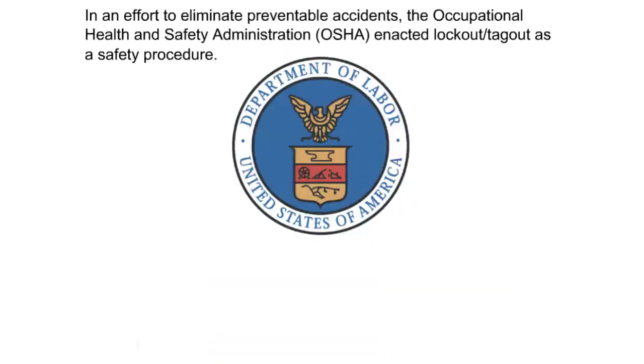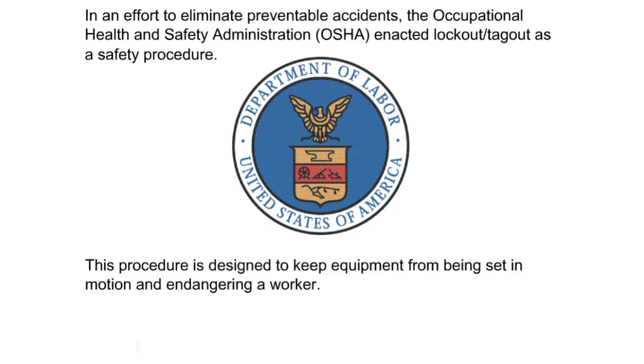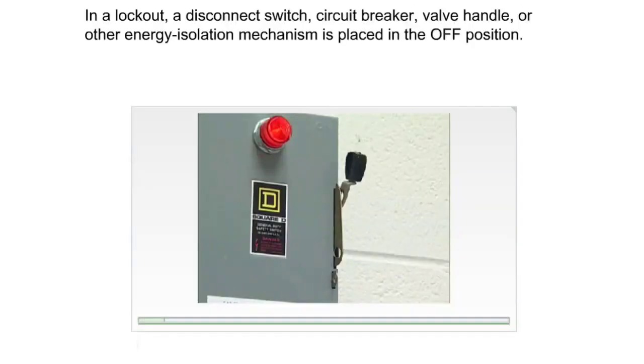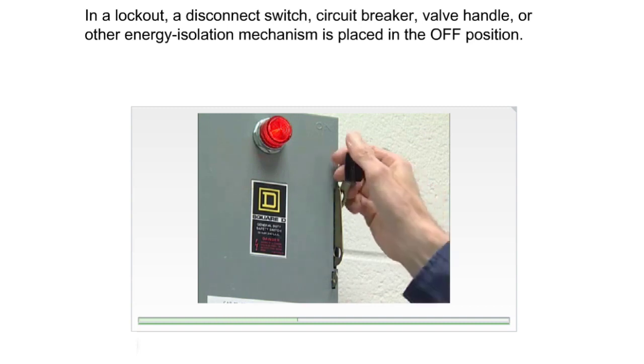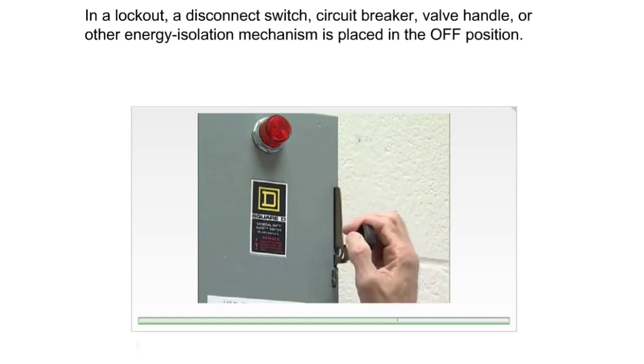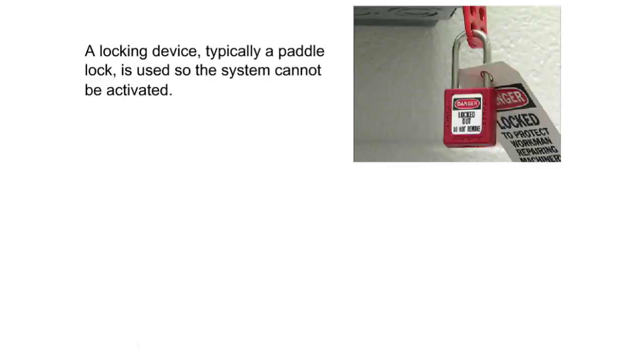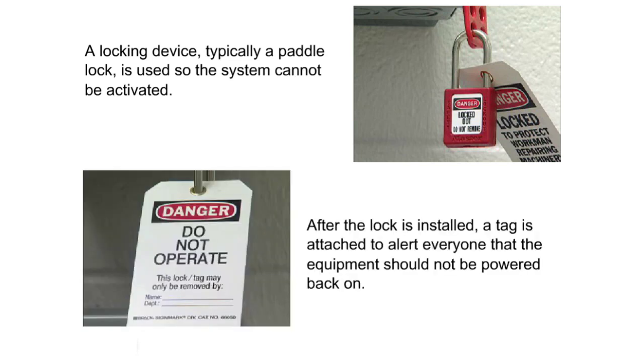In an effort to eliminate preventable accidents, the Occupational Health and Safety Administration, OSHA, enacted lockout-tagout as a safety procedure. This procedure is designed to keep equipment from being set in motion and endangering a worker. In a lockout, a disconnect switch, circuit breaker, valve handle, or other energy isolation mechanism is placed in the off position. A locking device, typically a padlock, is used so the system cannot be activated. After the lock is installed, a tag is attached to alert everyone that the equipment should not be powered back on.